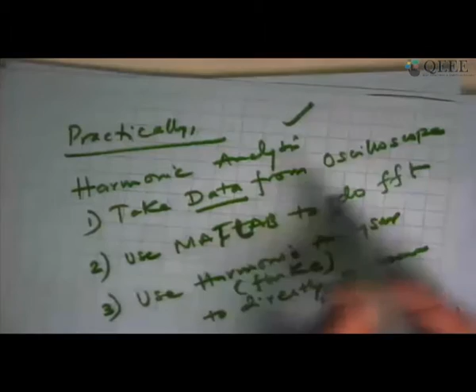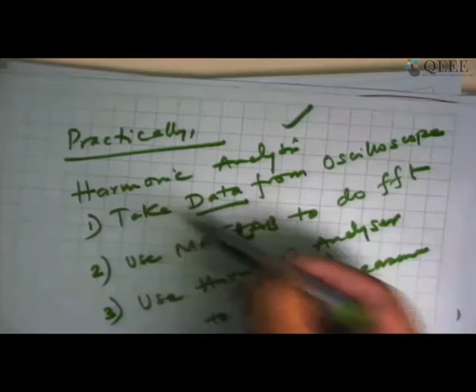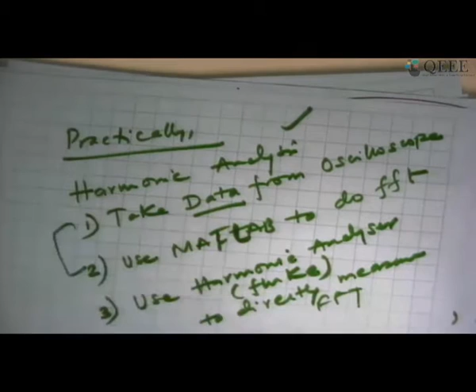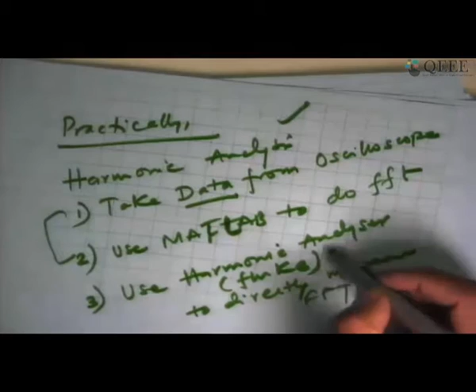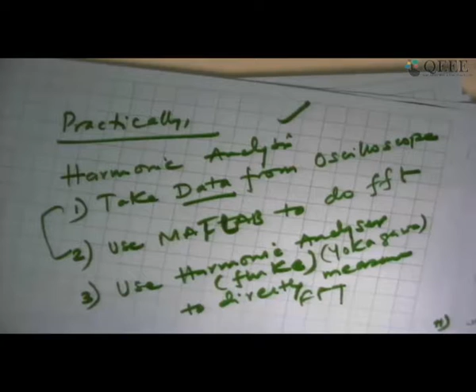First, actually there are two ways of doing harmonic analysis in practice. We generally take data from oscilloscopes. Now it's possible to save the data in MATLAB and do the harmonic analysis. This is one way. Or actually, if you have costly equipment like a harmonic analyzer from Fluke or Yokogawa, you can directly put the voltage probes across the line to line and get it. It will show you the harmonic spectrum. So this is the first way what we do in the lab.